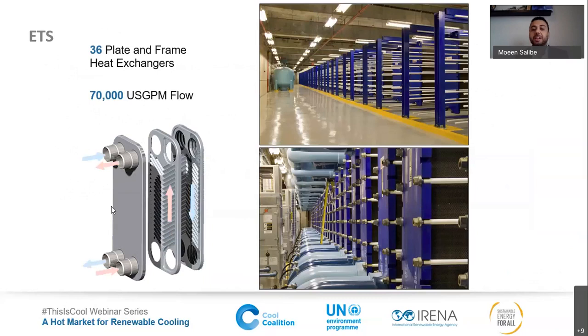This is a real picture from our ETS. As you see, there are no chillers, nothing in there other than 36 plate and frame heat exchangers with 70,000 US gallons per minute capacity. Excuse me, I haven't converted the numbers to SI units. We have three intakes coming from the lake at a capacity of 100,000 US gallons per minute, but we don't get this all the time—it's dependent on how much people are drinking the water. So we encourage people in Toronto to drink more water so we could have more capacity on our Enwave system.